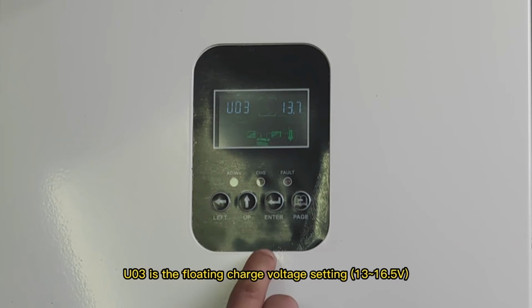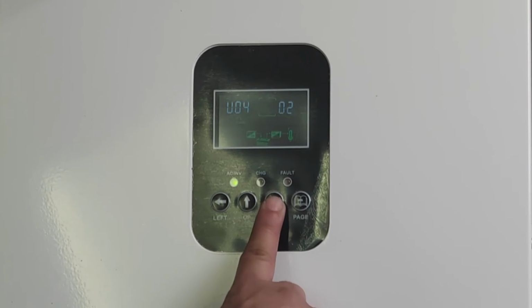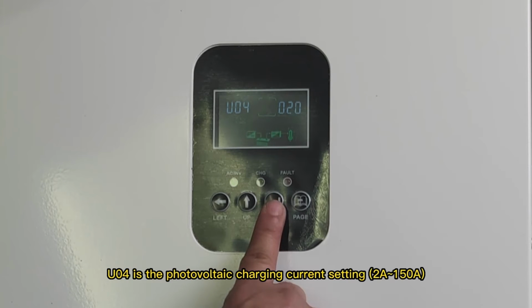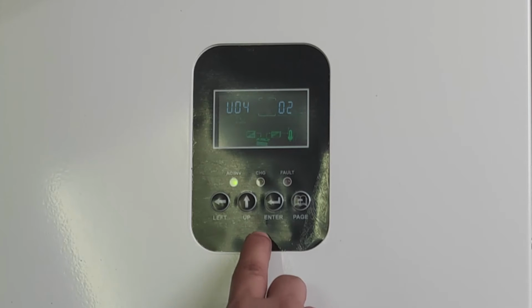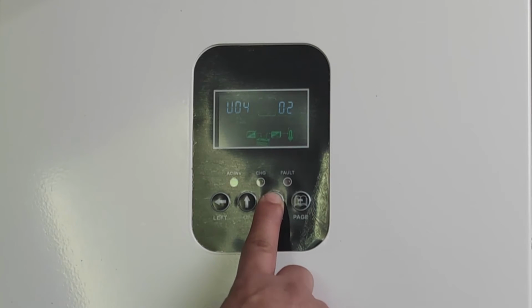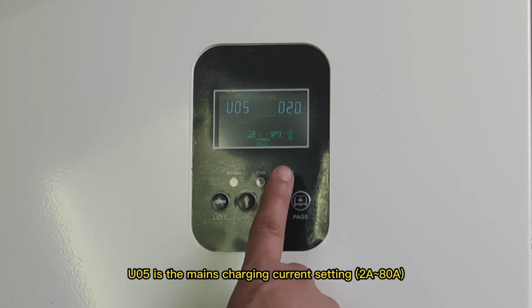U03 is the floating charge voltage setting, 13 to 16.5 volts. U04 is the photovoltaic charging current setting, 2 A to 150 A. U05 is the mains charging current setting.